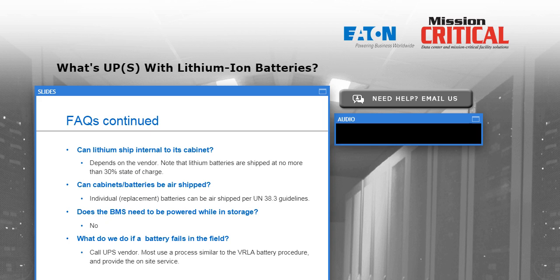Now, what do I do if I have a battery failure in the field? I've installed a battery system, it's up and running for a couple of years, and suddenly the management system tells me battery number 6 is bad. What do you do? Well, just like VRLA, you call the UPS vendor. We have processes similar to those for valve-regulated lead acid, and we can provide on-site service to come out, remove the defective battery, replace it with a new one, and get you back online and balanced up.